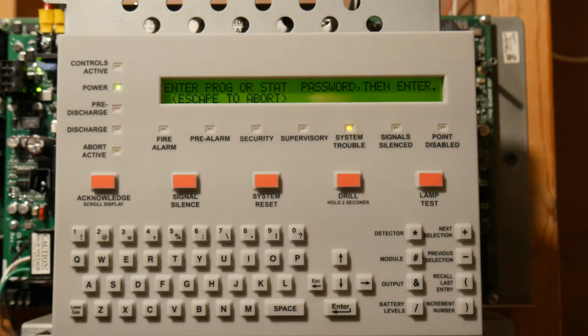With Notifier panels, there's a level 1 and a level 2 programming password. Level 1 gives you access to basic things like walk test, changing the time, clearing history, if I remember correctly. Level 2 gives you access to things like deleting the whole system, deleting points, changing sync options, big stuff. It's not like Simplex, where level 2 gives you access to level 1 and level 2. Level 1 and level 2 are separate. Whatever is in level 2, you don't have access to in level 1. But anyways, we're going to level 2 programming first.